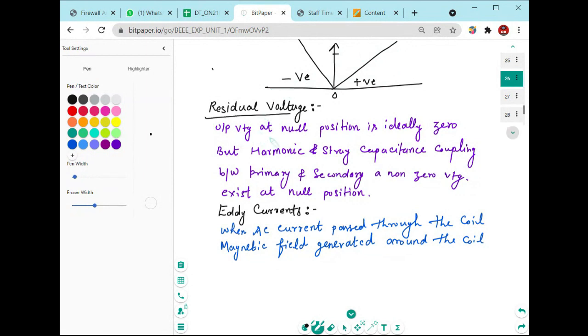The output voltage at null position is ideally zero, but due to harmonics and stray capacitance, or coupling between the primary and secondary, a non-zero voltage exists at the null position.